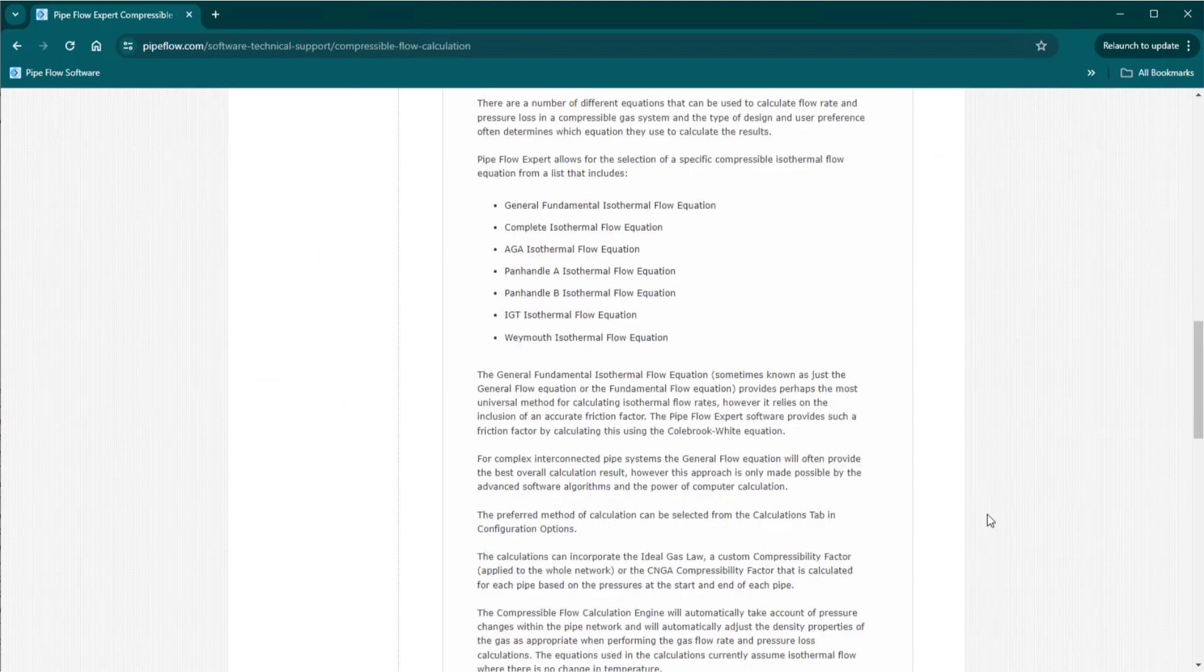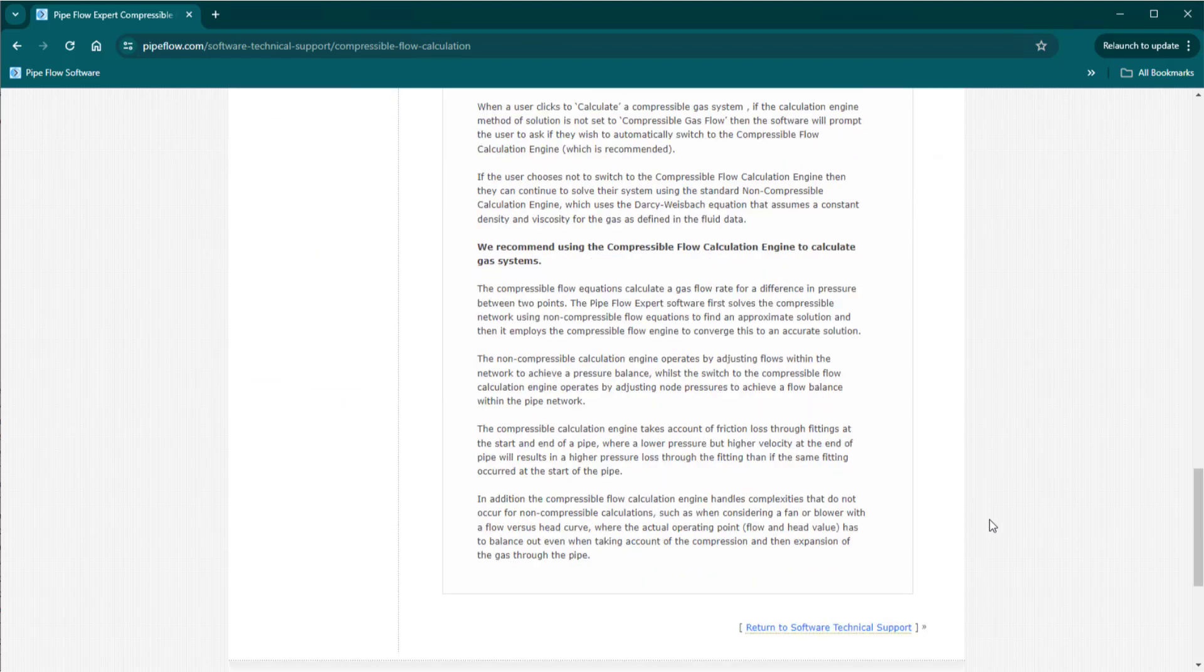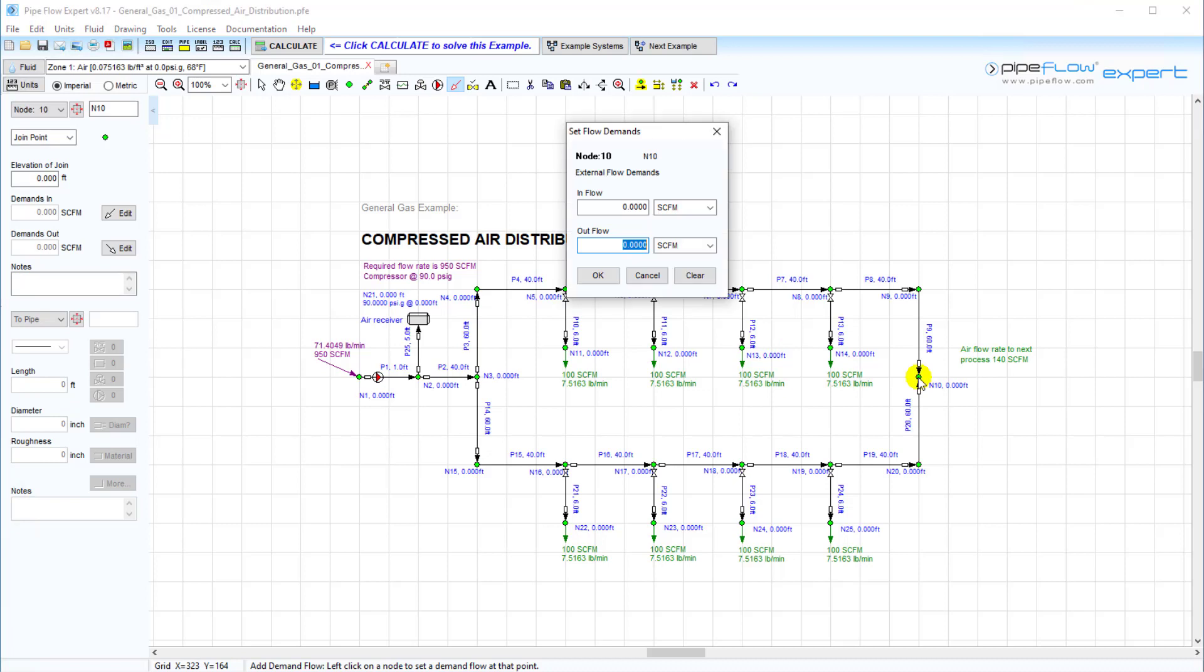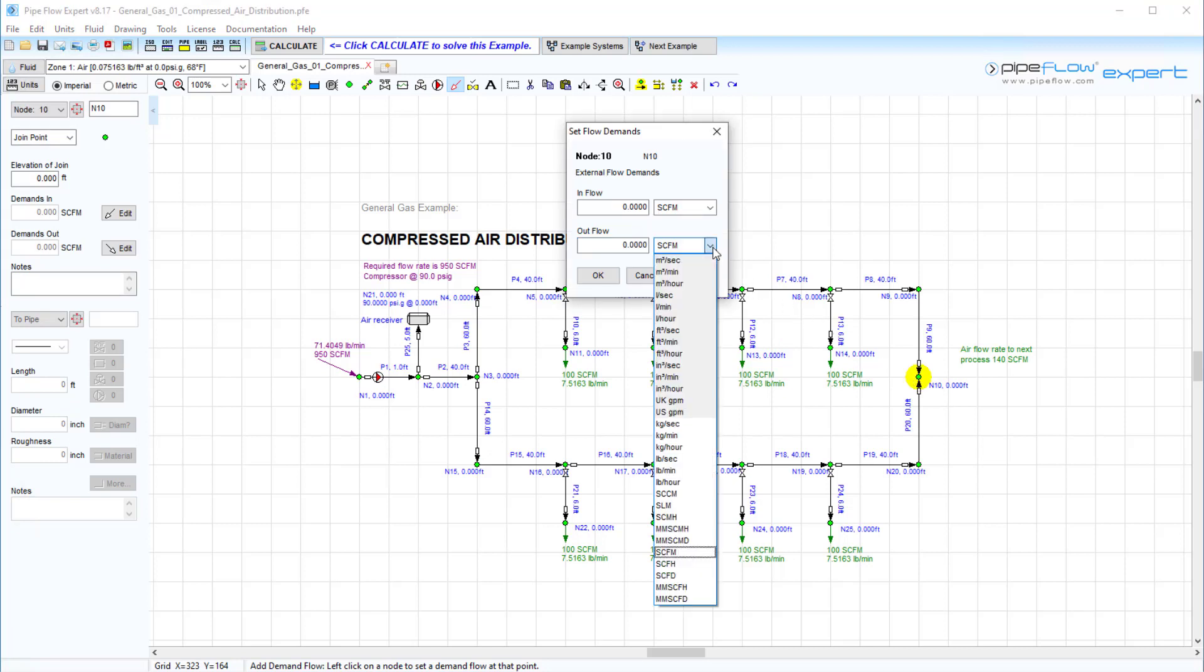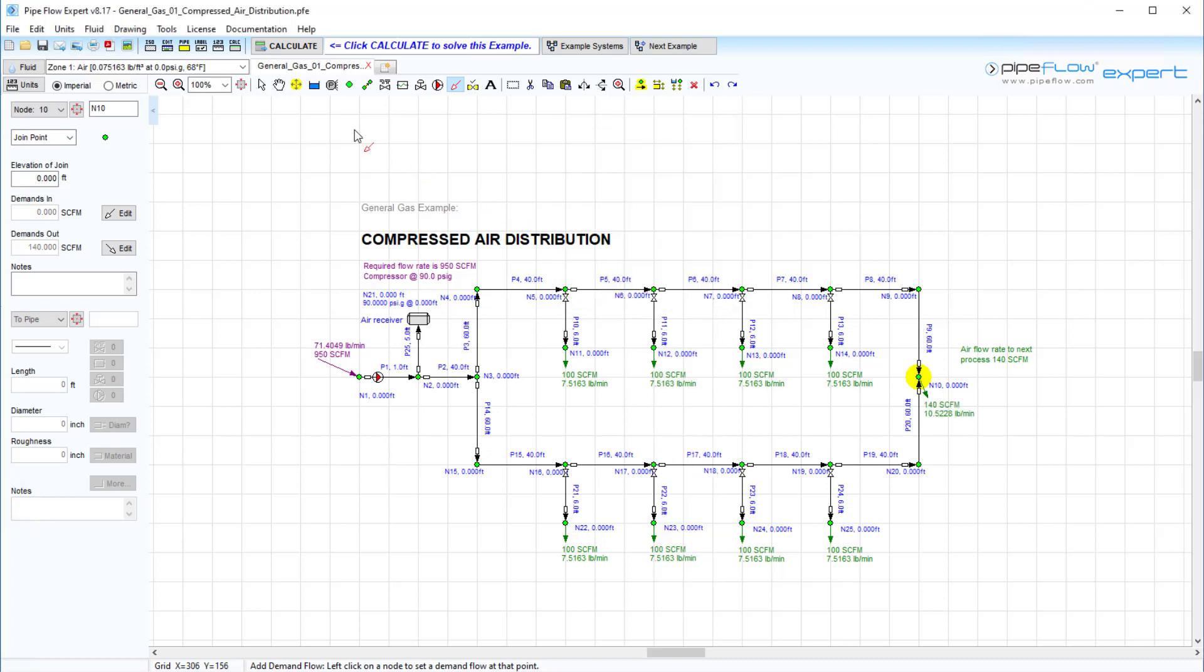There is some further information given on the FAQ page of our website pipeflow.com. When modeling with compressible fluids, since the volume and velocity change with changes in pressure, flow rate should always be specified in units of gas flow or mass flow, such as standard cubic meters per hour or kilograms per hour.